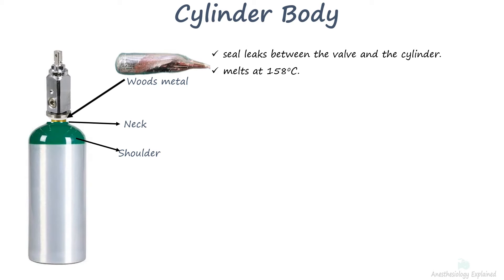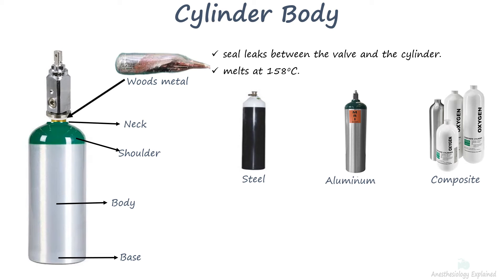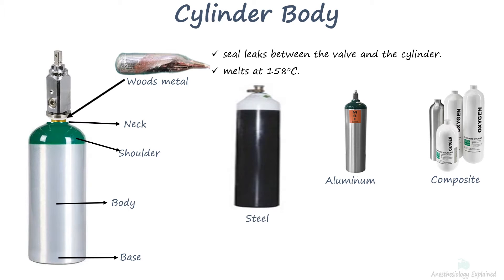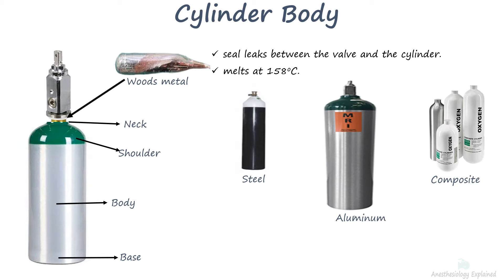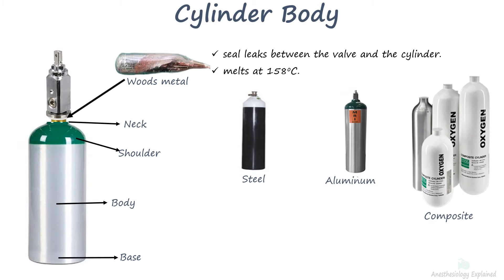Cylinders have a flat or concave base. The body of medical gas cylinders were traditionally constructed of steel, but now they are constructed of lightweight chrome molybdenum steel, aluminum, or a composite such as aluminum wrapped in carbon fiber.